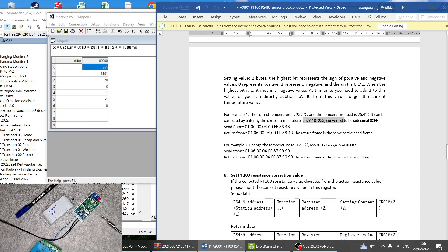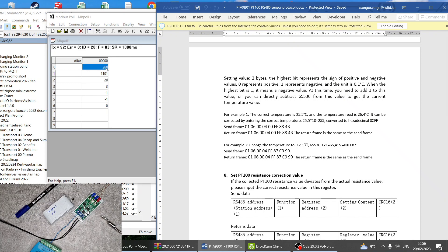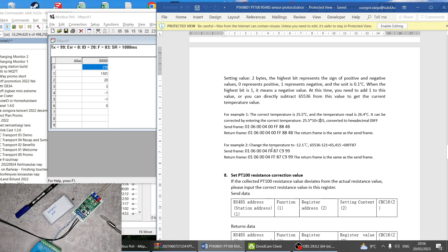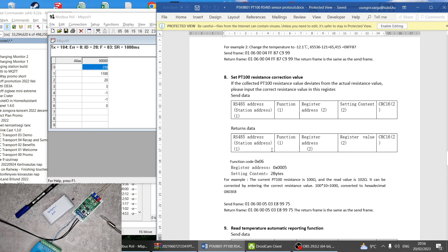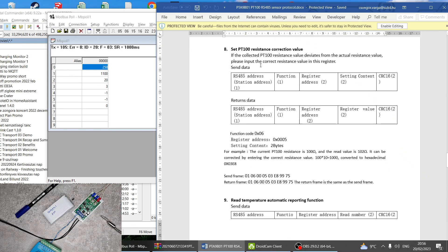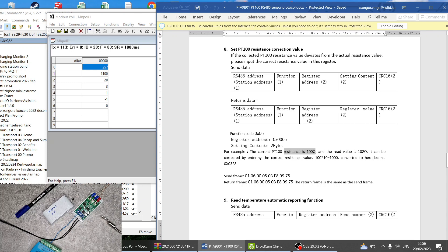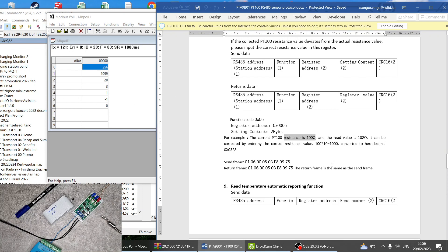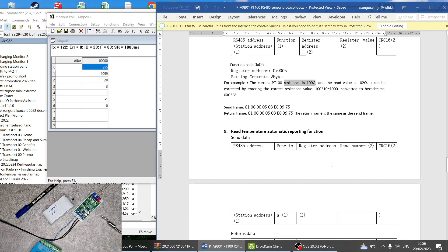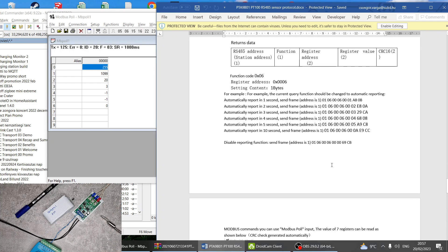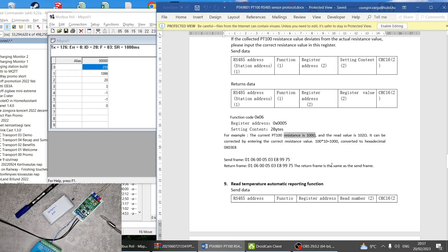So 25.5 times by 10, because all the values, well the temperature values are with one decimal place, so that's 255. You send 255 to the temperature correction and then it's going to, I guess internally, calculate the correction. Exactly the same with the PT100 resistance correction value - you send the value that you want to be measured at a particular time, so you send that to address 5 and then it's going to use that correction.